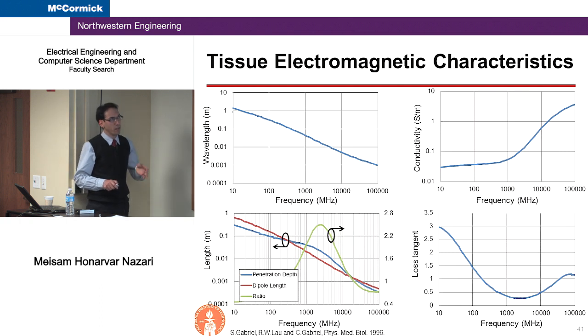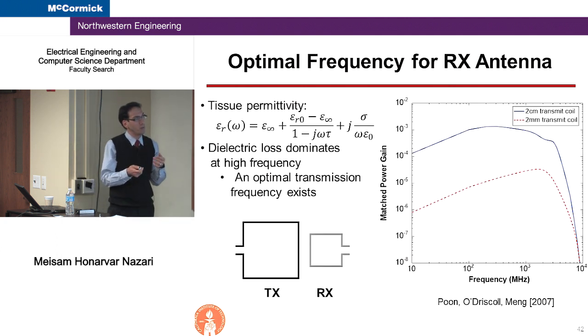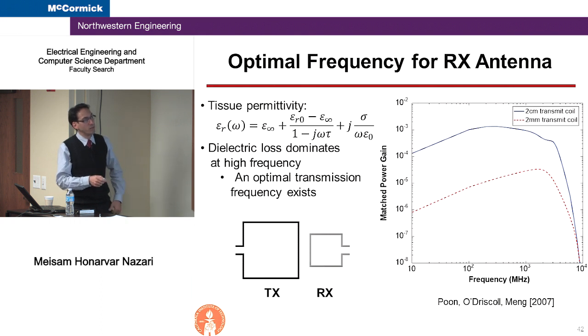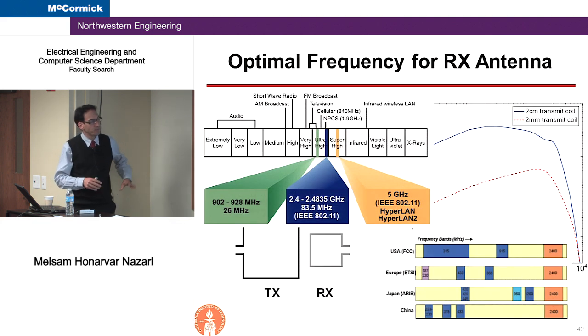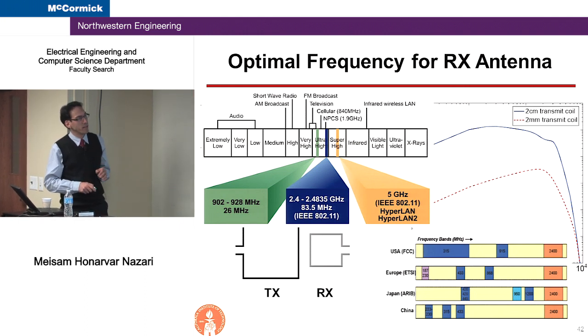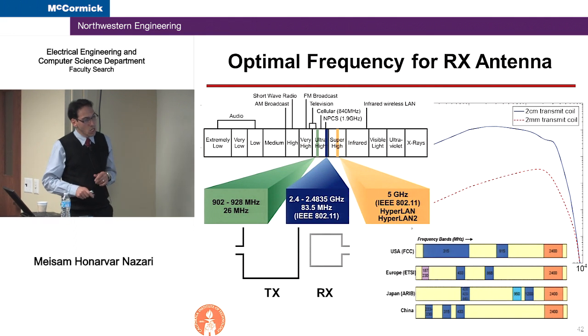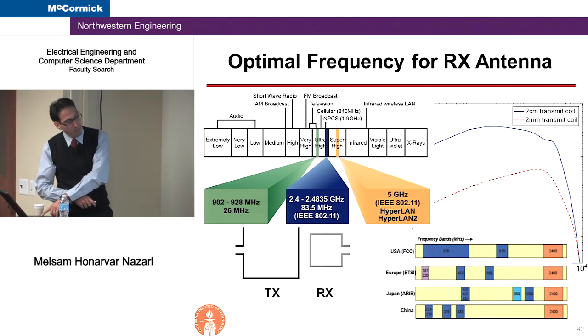But at the same time, we know from electromagnetic theory that in order to have a smaller antenna, we need to push our frequency higher and higher. So there should be an optimal frequency band that we could use to power our system that gives us the maximum power transfer. For example, for the case of two loop antennas, we can see that there is an optimal frequency band that we can use to power our device. The other constraint is that there are not many frequency bands available for these applications. So we are almost limited to ISM bands around 900 megahertz, 2.4, and 5 gigahertz. We have used this 900 megahertz band to do the RF powering.